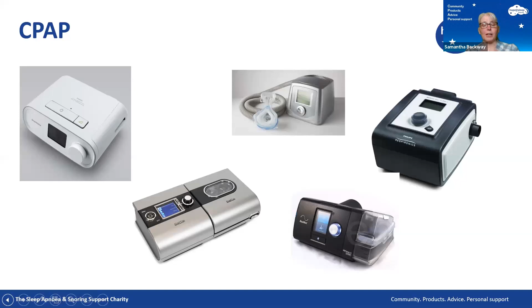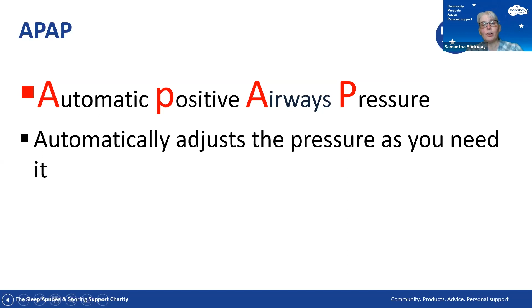APAP stands for automatic positive airway pressure, and this again is still a CPAP machine, and it's still going to give you a continuous pressure, but it automatically adjusts the pressure as you need it. It's got sensitive technology, and it looks at your breathing breath by breath, and it will automatically change it as you need it. So it's using sensitive algorithm therapy. Your breath is analysed breath by breath, and like I said, this will also sort of maximise the comfort that the machine will give you.